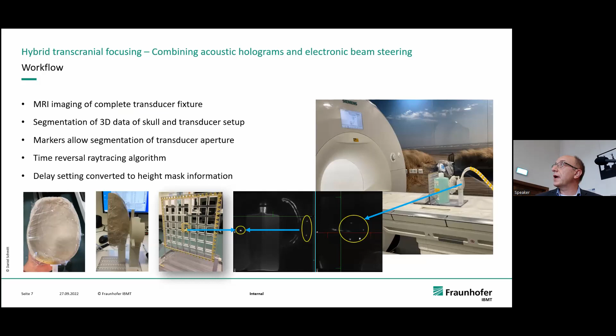So, a short look into the workflow. How do we get the data we need to make the mask? As I said before, we have this whole setup on the bed of the MRI. We have markers in the transducer fixture, so we can detect the transducer and the aperture, especially in the cross section and here in the sagittal section. We can also detect the target where we want to focus. With a time reversal ray tracing algorithm, we can calculate the delays required. And from the delays, we can calculate, using the velocity of sound, the height of the mask at a specific point.